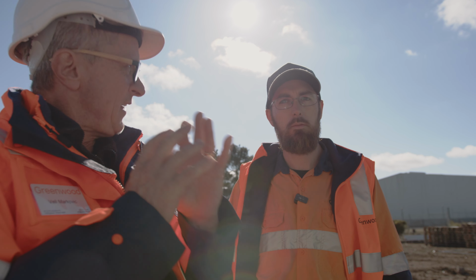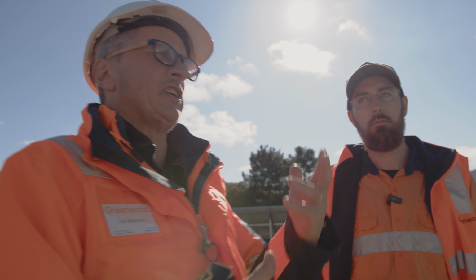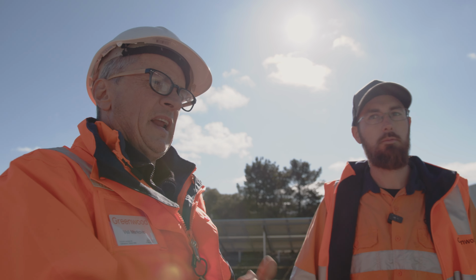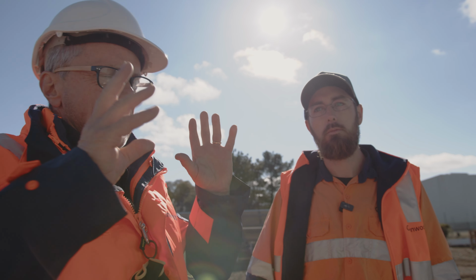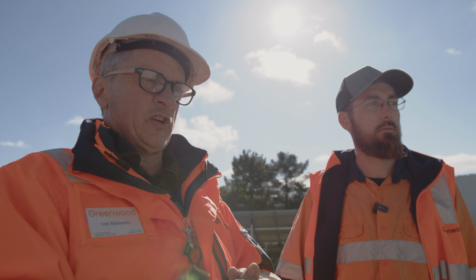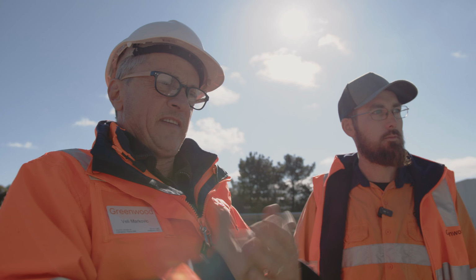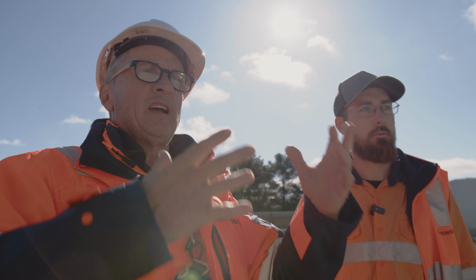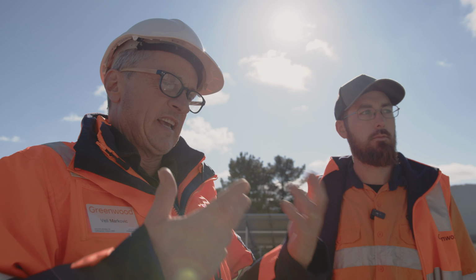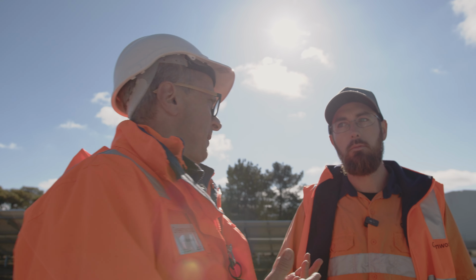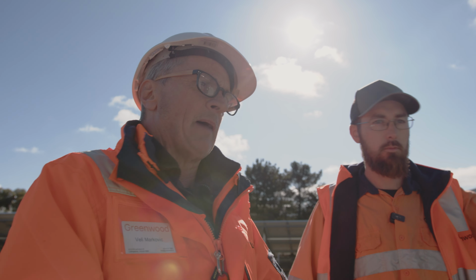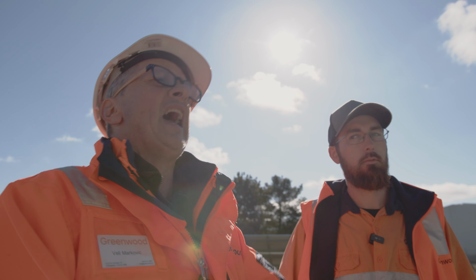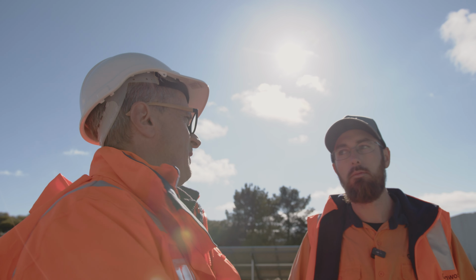That's a big thing to take into consideration if you are contemplating paralleling to save cabling. One, you'll have to do your cable calculations again to account for the fact that there's 2 strings being accommodated, in this case maybe 28 amps or so. Then you have to up the size of the cable, and you'll have to use some fusing and all the labour that comes with that.